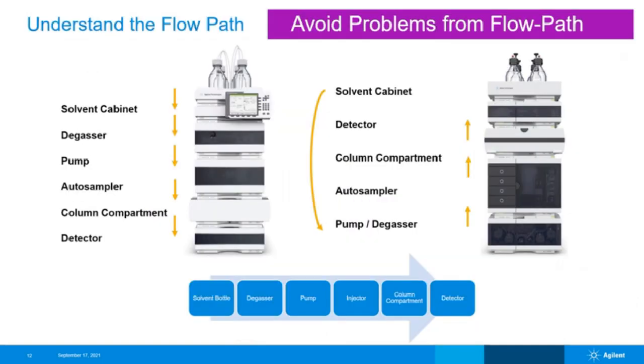When starting to think about the instrument flow path, it is important to understand the flow direction. The instrument setup may be different, but the flow path will be the same, going from the solvent cabinet to the degasser, the pump, the sampler, the column compartment, and finally the detector. Make sure you know the path of the flow in your instrument setup when you encounter chromatographic symptoms, which could be related to a blockage or a leak in your system. This best practice will help to reduce the troubleshooting procedures and keep the productivity under control.